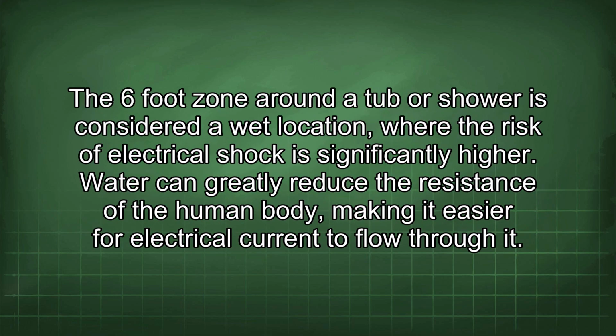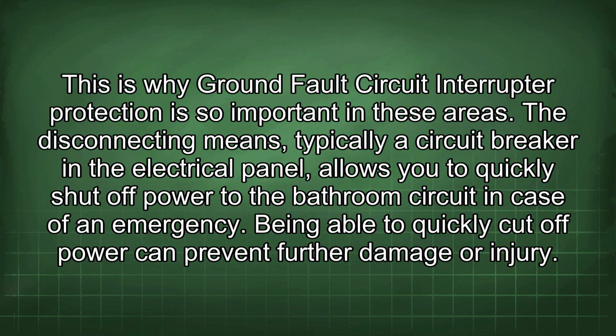shock. The 6-foot zone around a tub or shower is considered a wet location where the risk of electrical shock is significantly higher. Water can greatly reduce the resistance of the human body, making it easier for electrical current to flow through it. This is why ground fault circuit interrupter protection is so important in these areas.